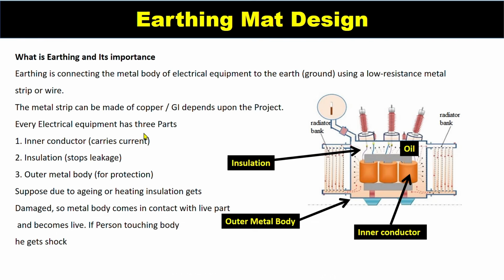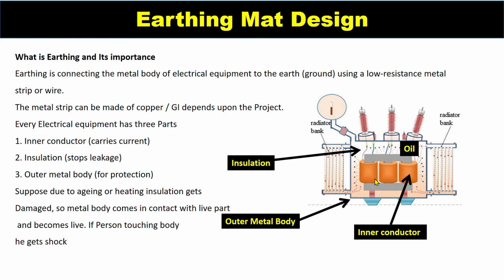Every electrical equipment has three parts. I have taken the example of a transformer. The three parts are the inner conductor that carries the current, which is the winding; the insulation that stops the leakage, where here oil is used as the insulation and in the windings we also use paper insulation; and the outer metal body, which is the tank of the transformer. This is the outer body.